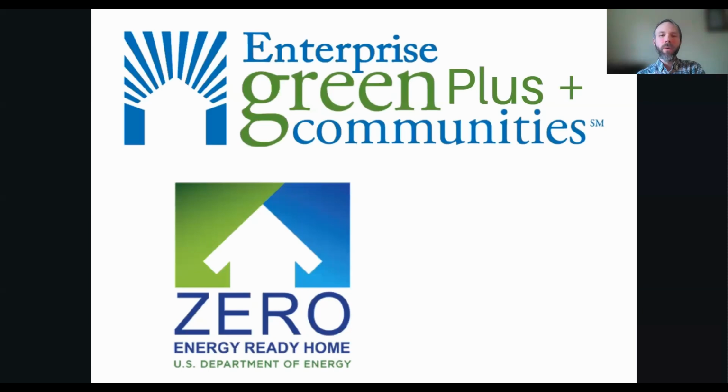The DOE Zero Energy Ready standard requires you to build a more energy efficient building than the code by beating ASHRAE 90.1-2019 by at least 20% in energy conservation. Then you need to prepare the building for future solar. You do not need solar on it for now during this certification process. Then you need to follow the Indoor airPLUS standard, which ensures good air quality in the building. And again, it's in line with the Enterprise standards that are available.